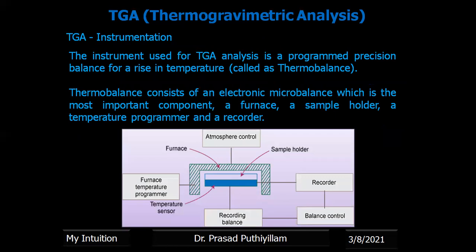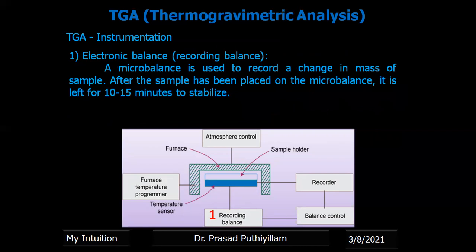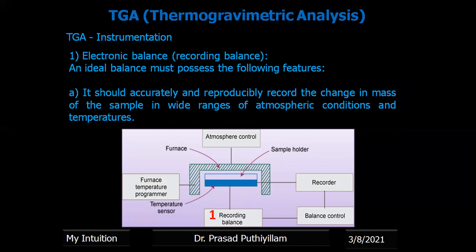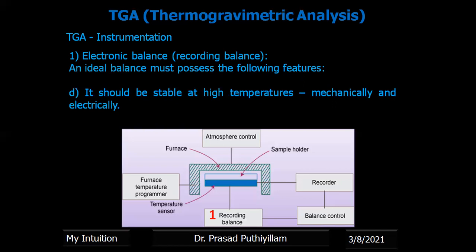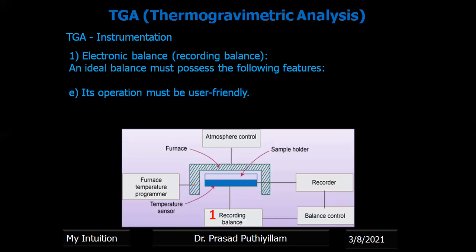The instrumentation of TGA — the instrument setup — is called a thermo-balance. The thermo-balance consists of a micro-balance, a furnace, a sample holder, a temperature programmer, a temperature controller and a recording system. The micro-balance is used to record the change in mass. The sample is kept in the micro-balance and left for 10 to 15 minutes to stabilize. An ideal balance should accurately and reproducibly record the change in mass in wide ranges of atmospheric conditions and temperatures, provide an electronic signal to record changes in mass, have rapid response to change in mass, be stable at high temperature both mechanically and electrically, and be user-friendly.